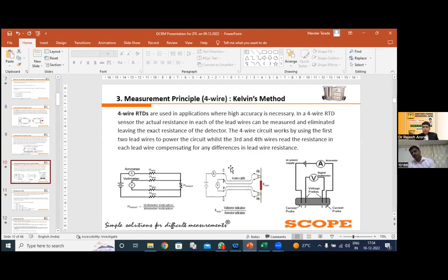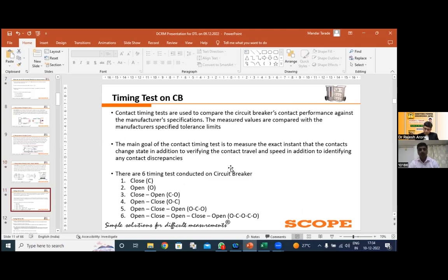Moving ahead, the timing test on the CB. Why do we need to perform the timing test? As per the IEC standard, we are performing different timing tests on the CB. But why is the timing test required? Because the timing test is used to compare the circuit breaker's contact performance against the manufacturer specification. So whether you are getting the contact timing well within the specified limits or not, even with the help of the software, you can do the trend analysis of your timing. And if it is exceeding the limits, then you need to set the timings right.